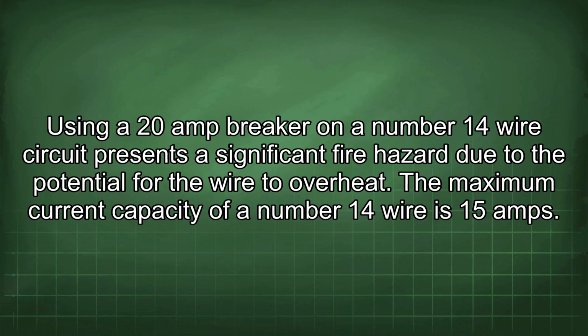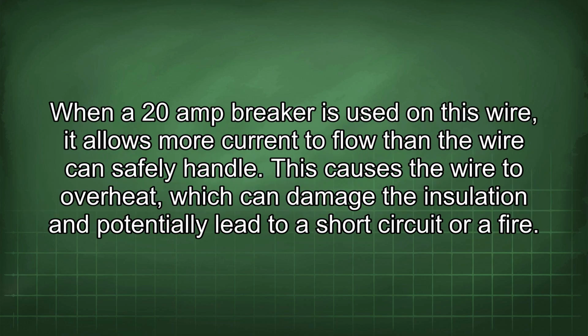Using a 20 amp breaker on a number 14 wire circuit presents a significant fire hazard due to the potential for the wire to overheat. The maximum current capacity of a number 14 wire is 15 amps. When a 20 amp breaker is used on this wire, it allows more current to flow than the wire can safely handle.